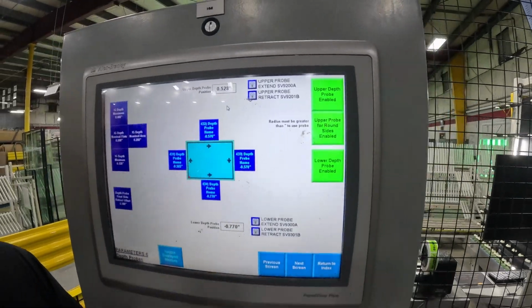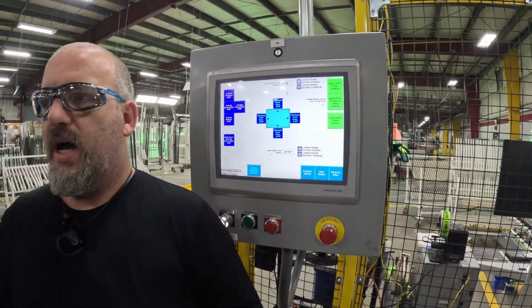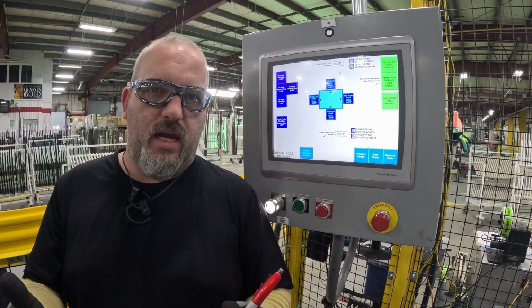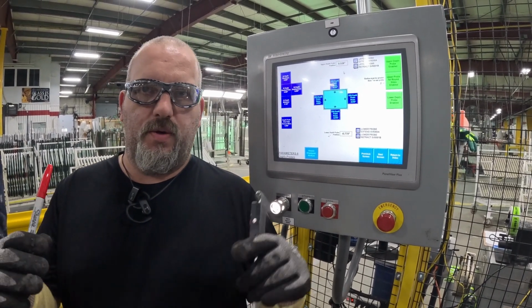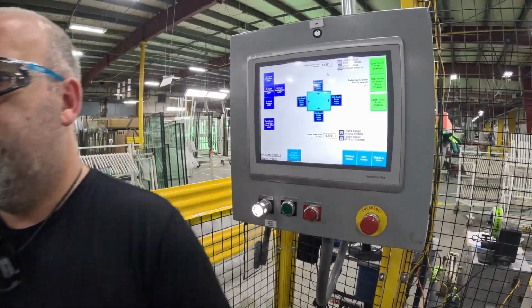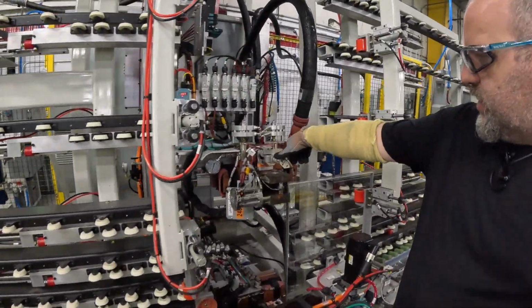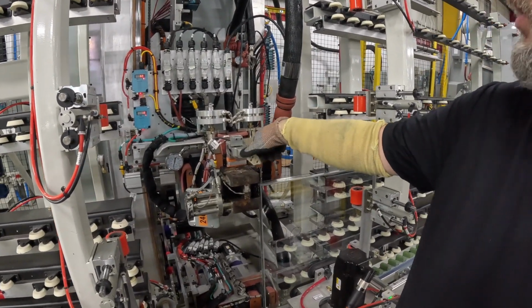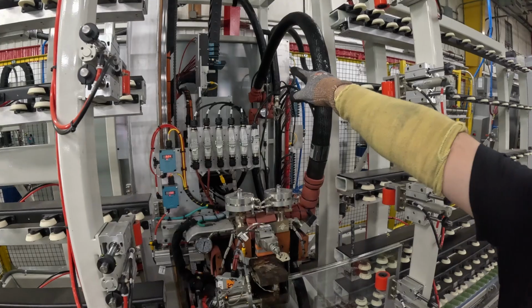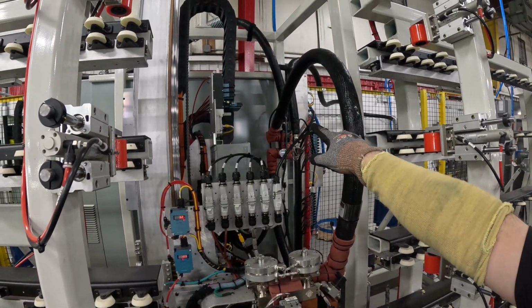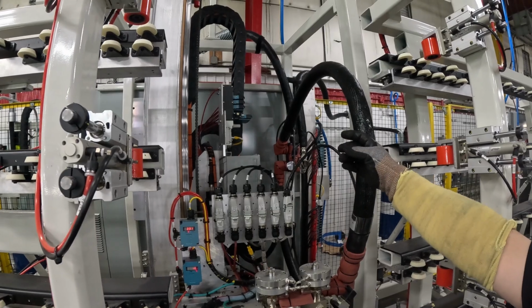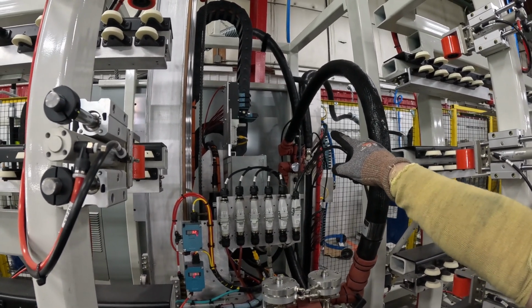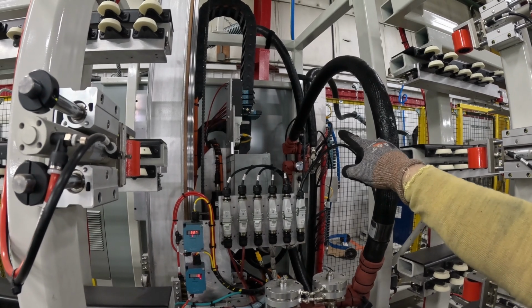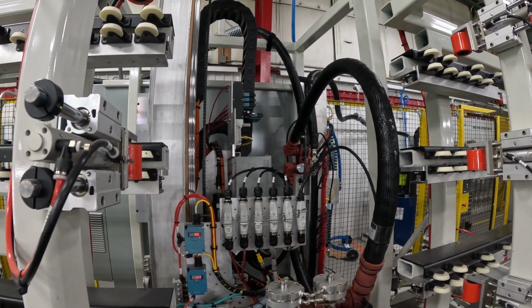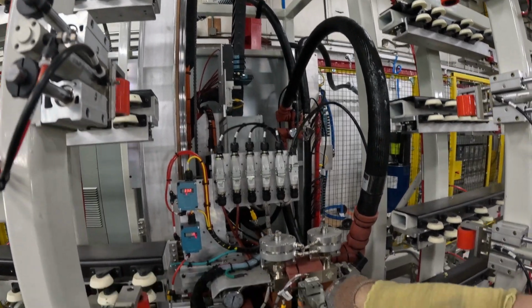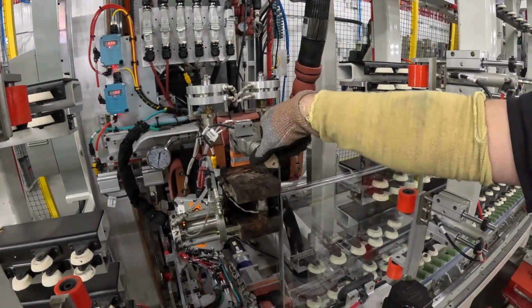If it changes a lot, like let's say it went from 220 to like 190, that indicates that you might have too much pressure on the depth probe. The pressure, we run about 10 to 15 pounds on these depth probes. If you look on that valve bank up there, there's a little pressure regulator poking out the side with a gold screw. It's that bottommost one on the stack. That's where you can adjust the pressure. Once they're set, you typically shouldn't have to adjust them. But that is where you would adjust the pressure for your depth probe.